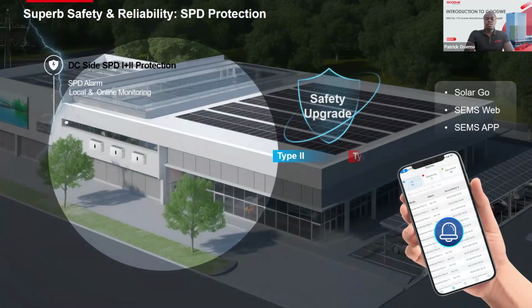The generation capacity of your system is also impacted by how safe your system is. Now with GoodWe, in areas that are not that frequent with lightning strikes, the type 2 is okay. If you're installing your inverter in a lightning-prone area, then we have the type 1+2, which is optional. With this, you can get alerts on the status of your surge protection device using our in-house software like the SolarGo, the SEMS Web, and the SEMS Plus applications. With this, you could get alerts on the status of your SPDs, which makes operation and maintenance easier.